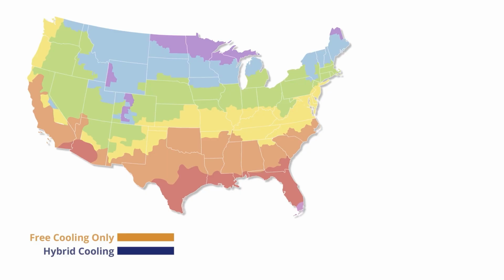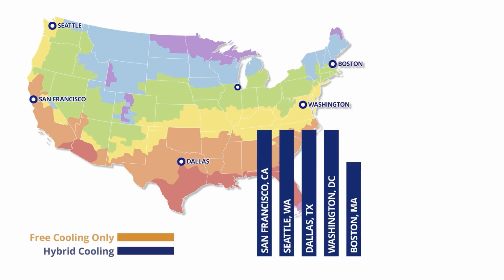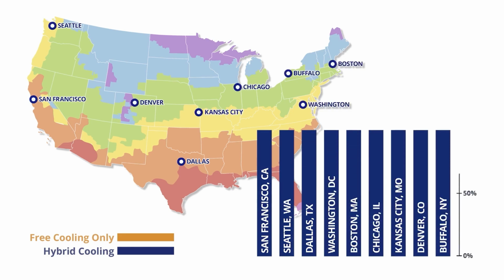It's important to note that when ambient temperatures allow a system to take advantage of free cooling, a large majority of the hours occur in the hybrid mode. For example, in data center applications, it can range from 70 to 100% of the operating hours. Therefore, maximizing the free cooling capacity, especially in the high-hour hybrid mode operation, will be key to optimizing your energy savings goal.